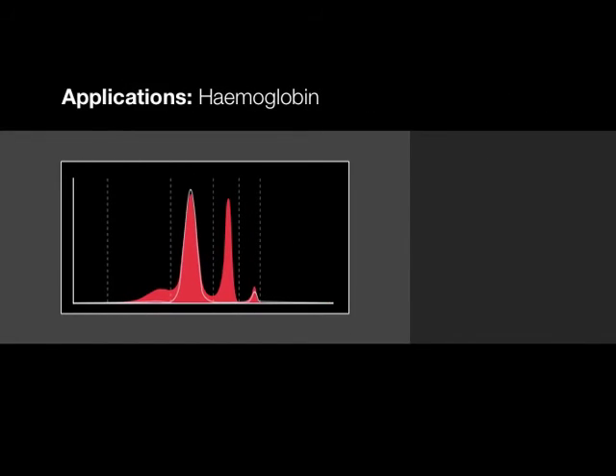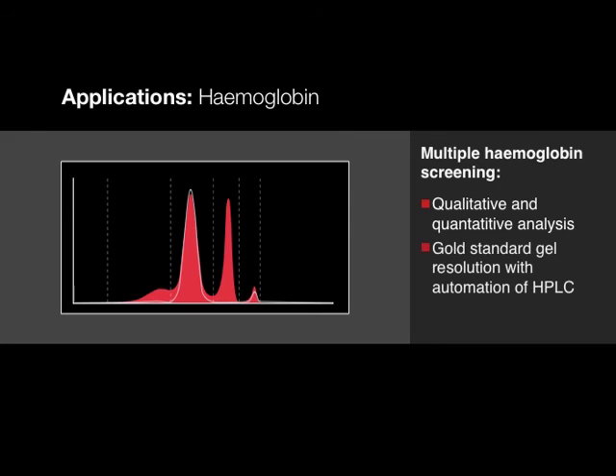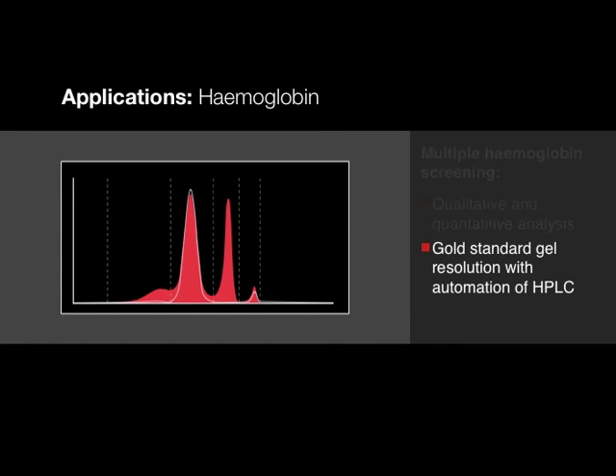The V8 haemoglobin isoelectric focusing assay is designed for screening and diagnosis of multiple haemoglobin disorders. Within one assay, the V8 can deliver qualitative and quantitative haemoglobin analysis.